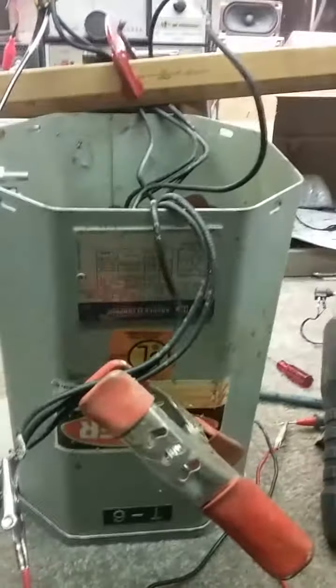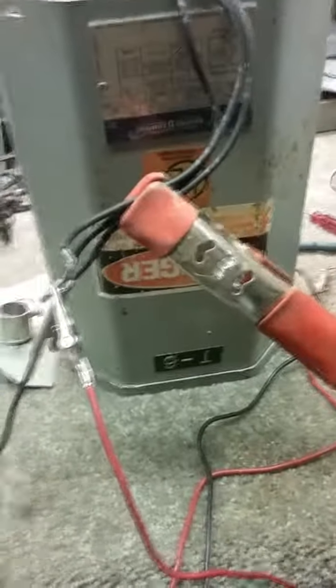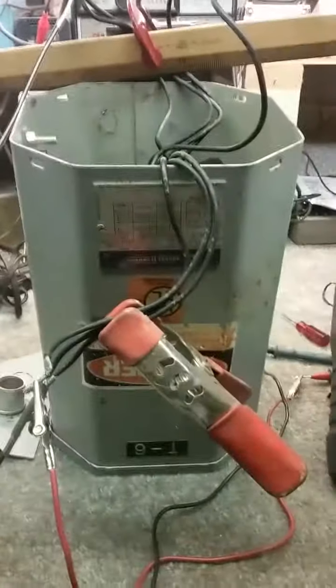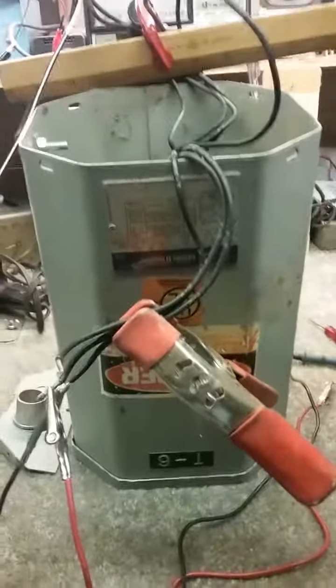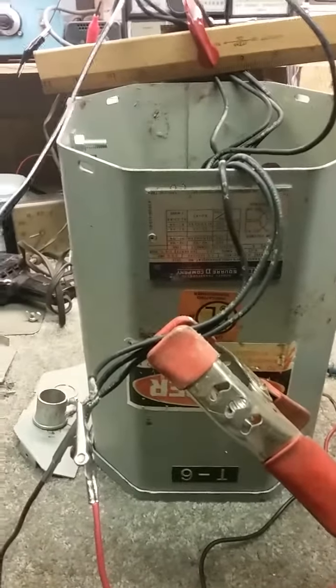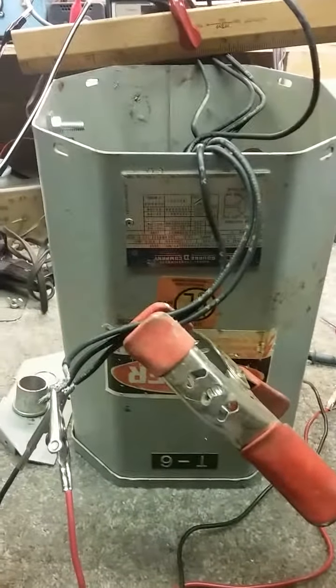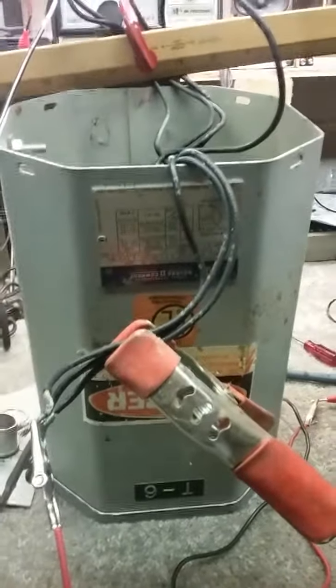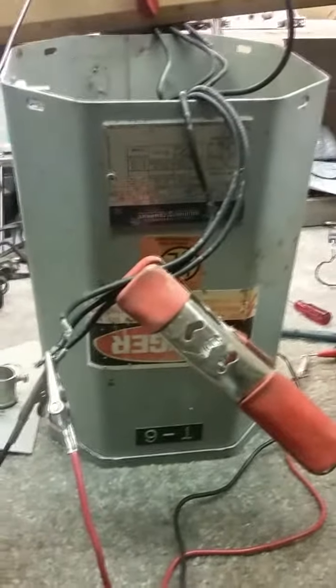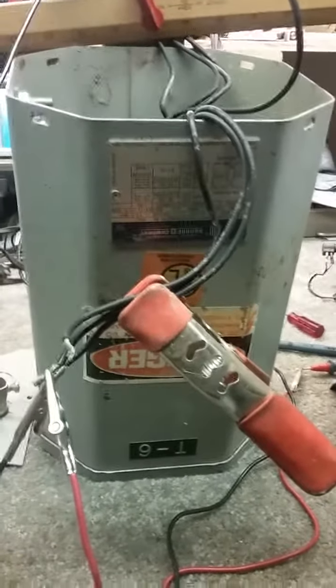So, if someone tells you that you can't check a transformer like this, or even a bigger one, because of the power consumption requirements, no, that's not the case. What you can't do is give it the input voltage that it's designed to use if you cannot provide the amount of current that it's going to take. And this is an issue that a lot of people have. I'm going to go ahead and shut this off. This is the issue that a lot of people have with transformers. They don't understand how transformers work.